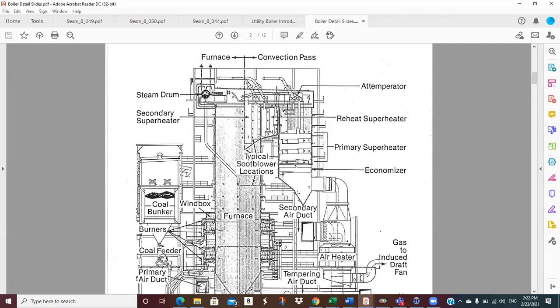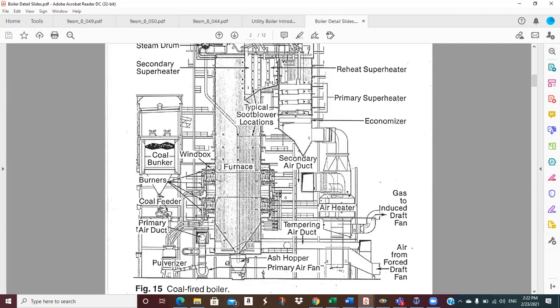So here's your ducting. Here's your air heater. This hot gas is probably down 500-600 degrees, maybe 700. We'll go through the air preheater, and of course we're taking the air from the forced draft fan and preheating it before we blow it in, so that helps reduce the amount of fuel that we use.